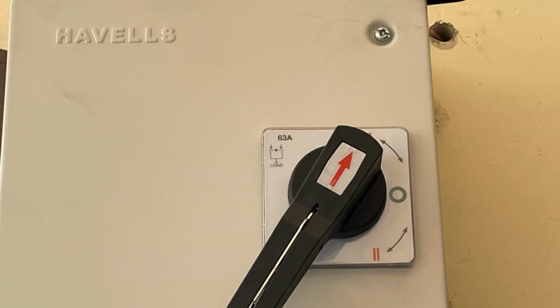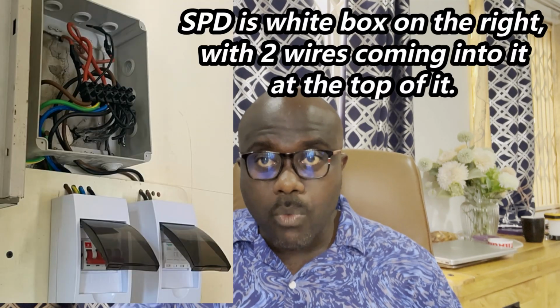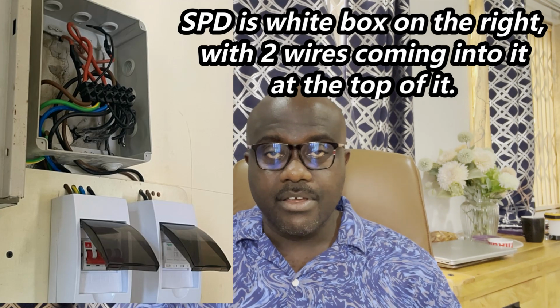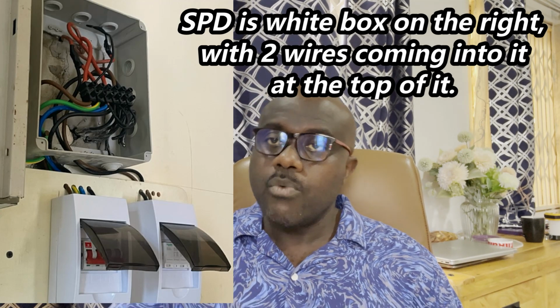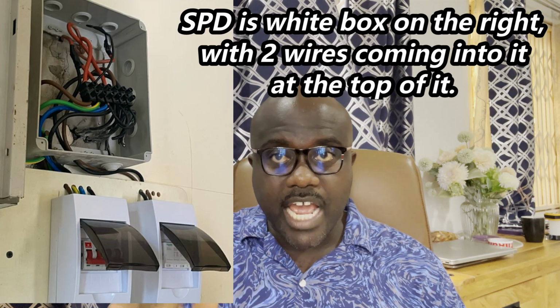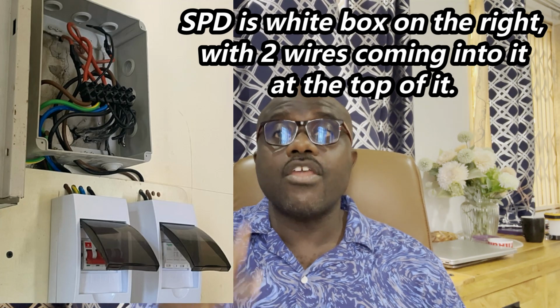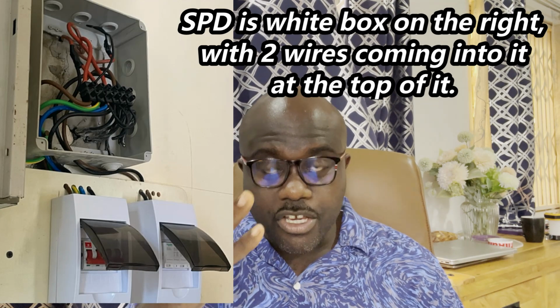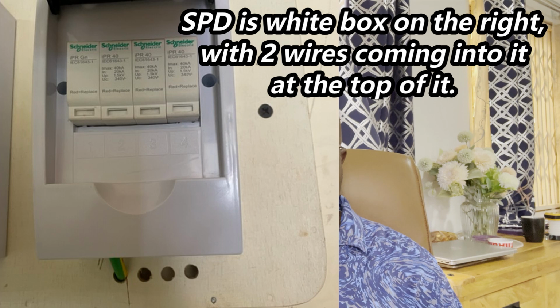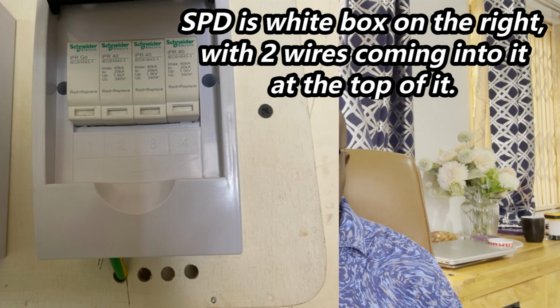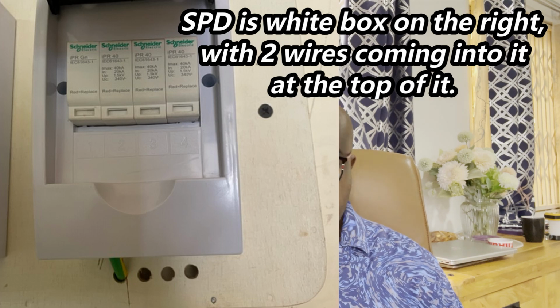Then from the changeover, I then went into this client's electrical room to have a further look at the installation. So the client has very smartly got his electrician to put in a surge protective device, SPD, again, picture on your screen. But for some strange reason, the electrician had only wired 2 phases and then to earth. Well, what's going on here? When you look at the manufacturer's detail wiring diagram on the side, it clearly tells you wire in all the 3 phases and the neutral, and then wire in the earth connection. The wiring details are on the side. That's the instruction from the manual. So why do something different?